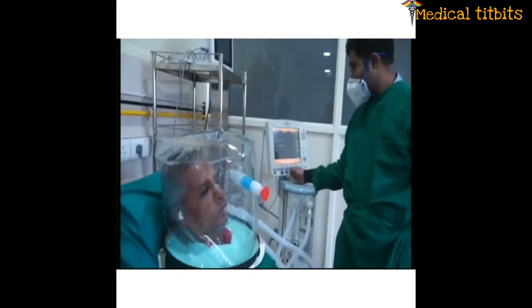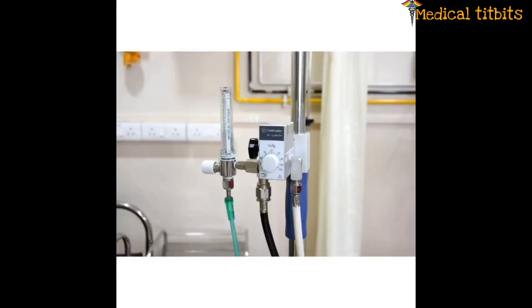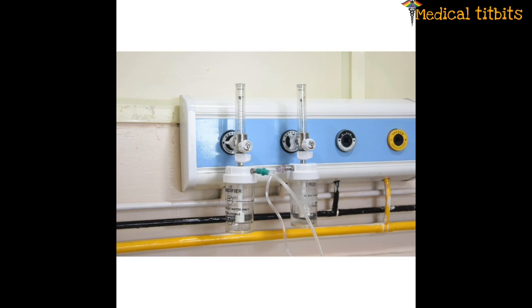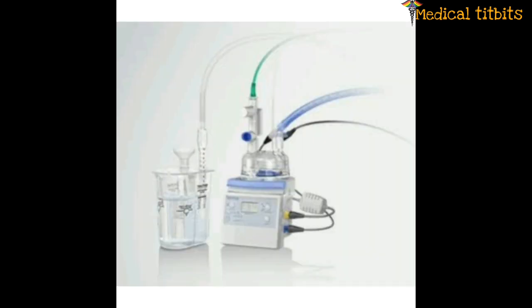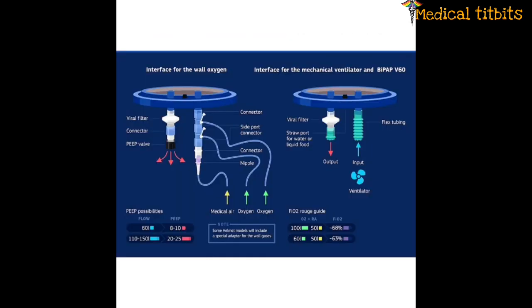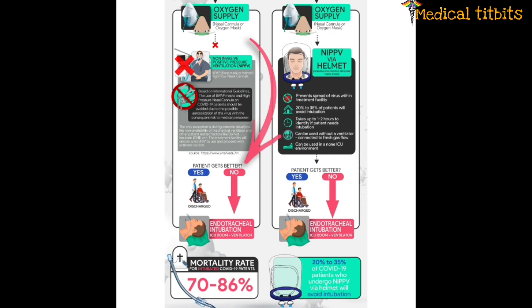The helmet can be attached to a blender with flow meter, wall oxygen with medical air, ventilator, CPAP and BiPAP. For the wall gas, the inspiratory limb can be connected to the medical air, oxygen, flow meter. The expiratory limb is attached to the viral filter and PEEP valve. 20 to 35% of the patients will avoid intubation.